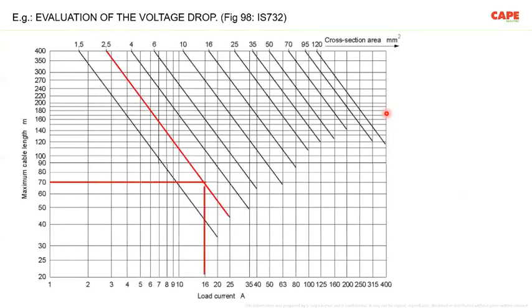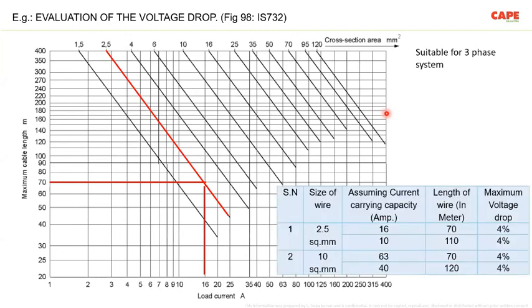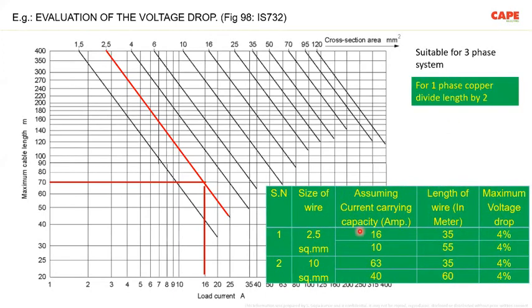These calculations are also very well included in the IS 732 standard. I am showing you a picture, figure 98 from IS 732, on how to select the wire for a 3-phase system. For example, for a 2.5 square mm wire at 16 amps, you can use up to 70 meters, but that is for 3-phase application. For single-phase application, with 2.5 square mm wire, the maximum cable length is 35 meters. Why I'm showing this is that all these calculations must be followed properly.